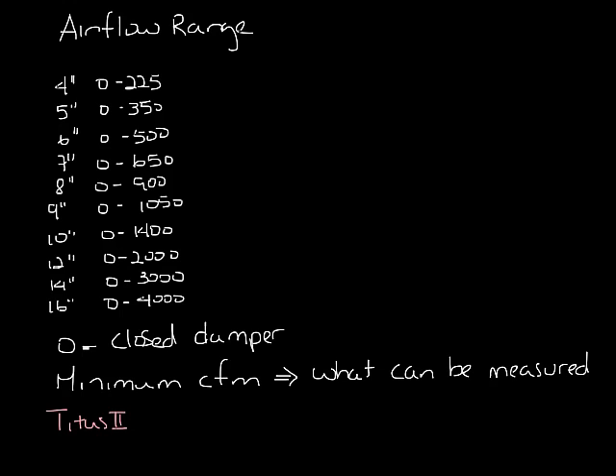For instance, our Titus 2 pneumatic controller can control down to 145 CFM on an 8-inch inlet, but the Titus 1 only goes down to 190 CFM. And then someone else's DDC controller could even go lower than that, maybe. So it's really dependent on what the controller can handle.